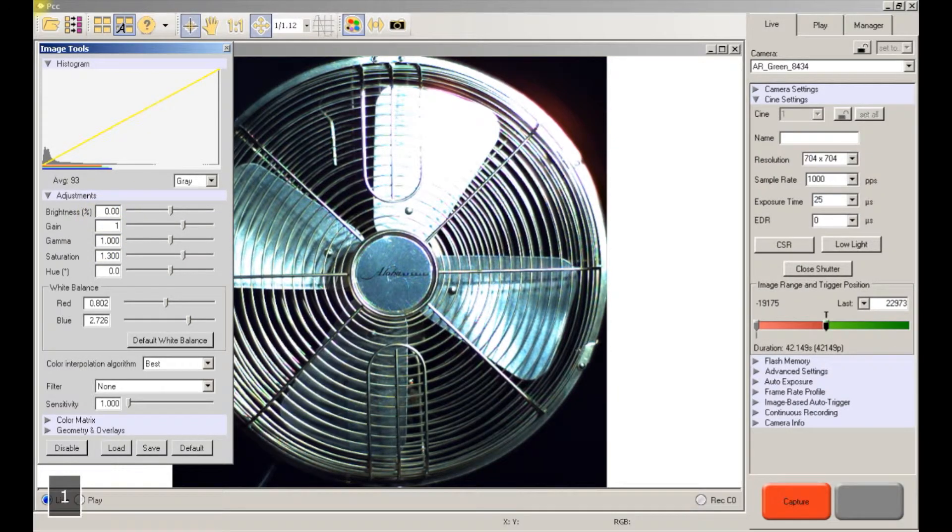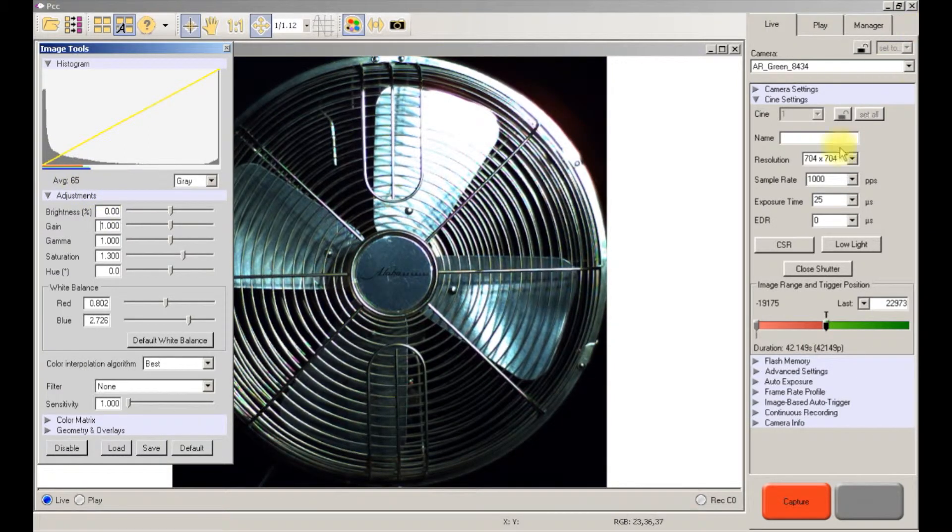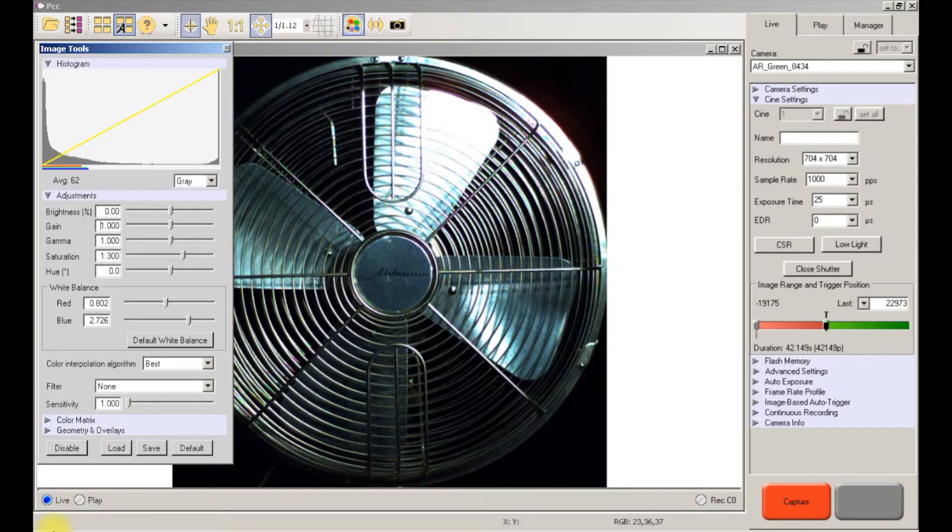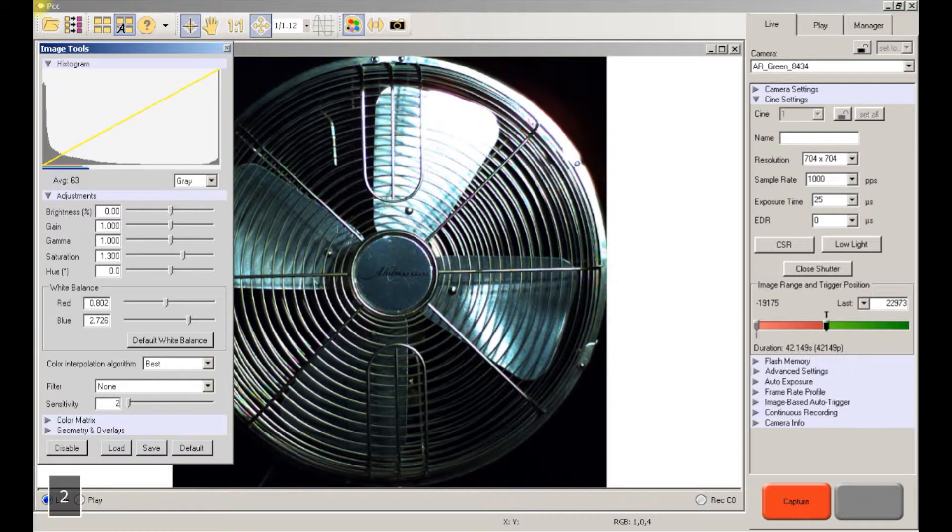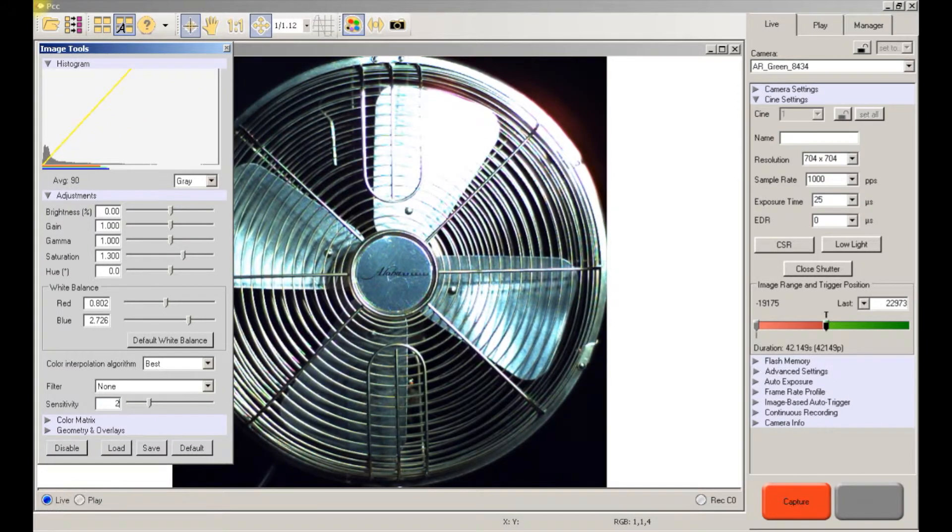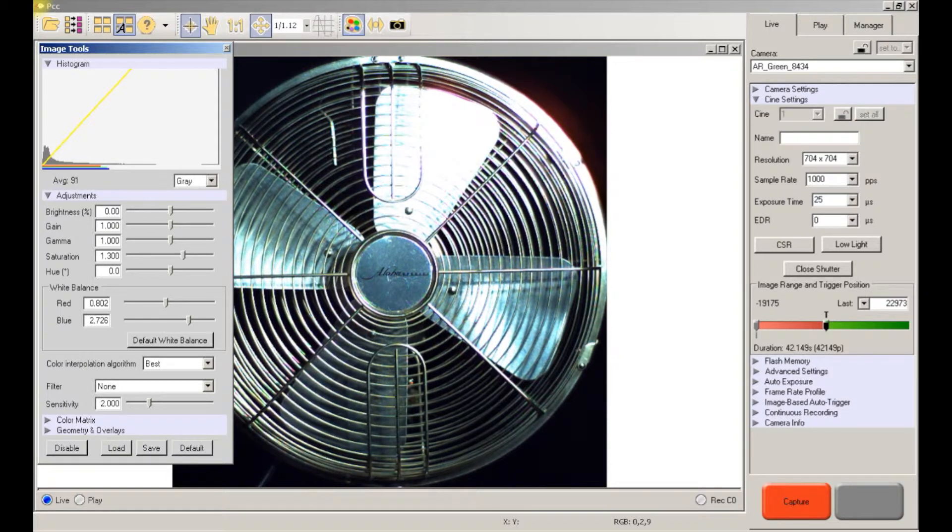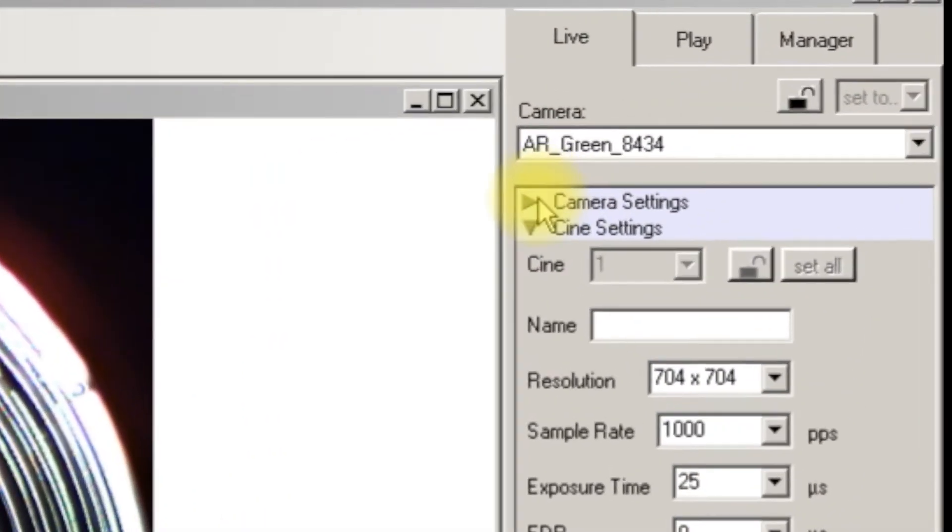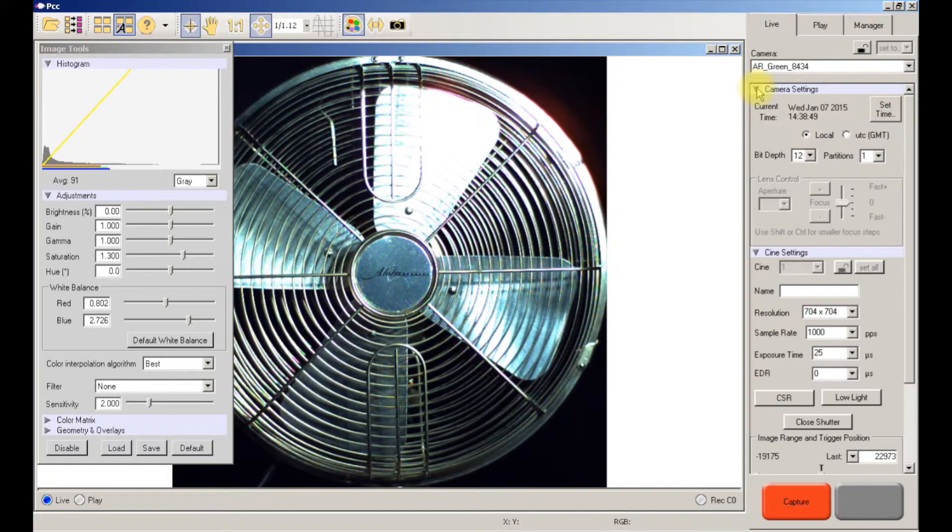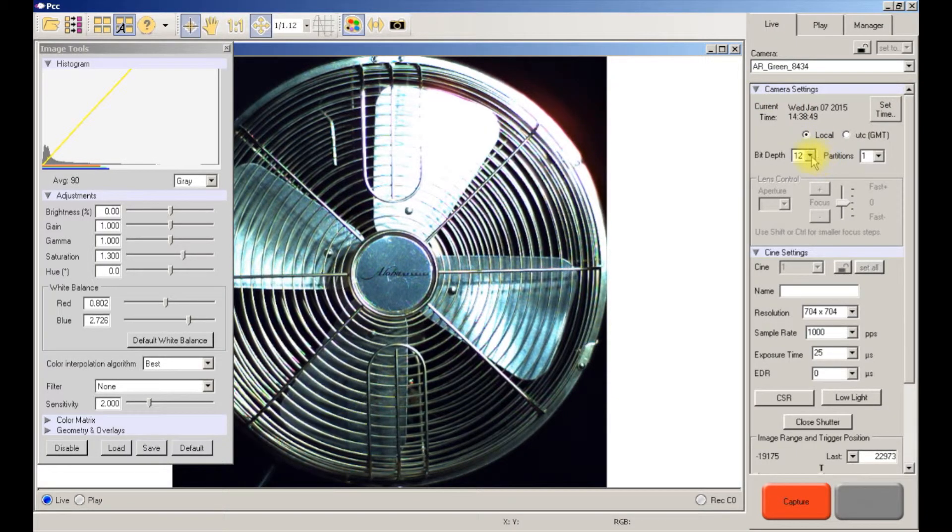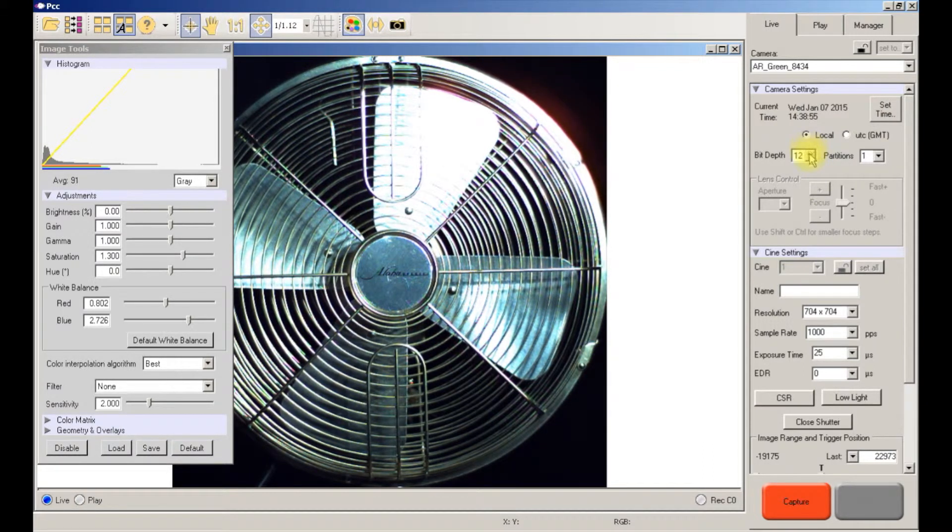So again it's darker at 25 microseconds. We're going to change the sensitivity now. The sensitivity is only available if you're recording in 12 bit image depth. So that would be over here in your camera settings, here's where you'd select the image bit depth. If it's on 12 you'll have the sensitivity available, if it's not on 12 you will not have it available.